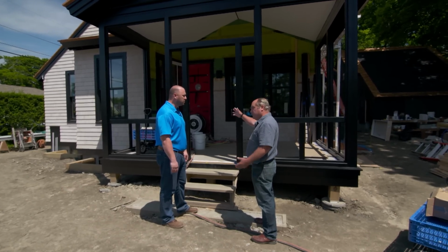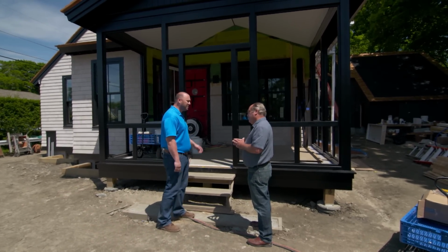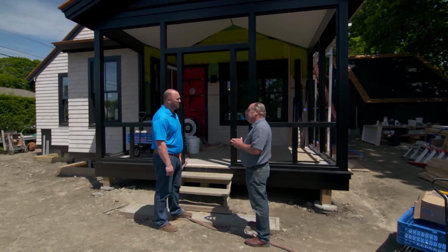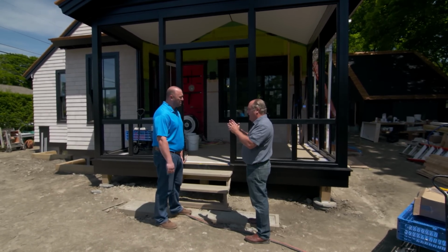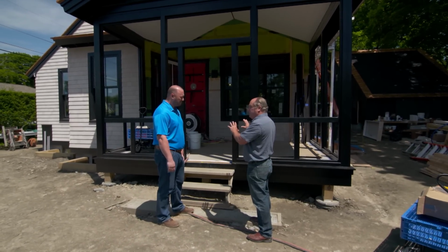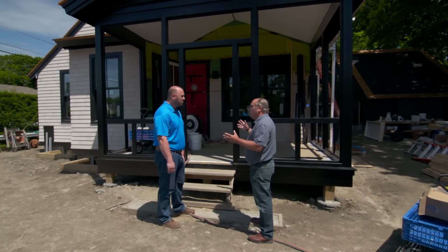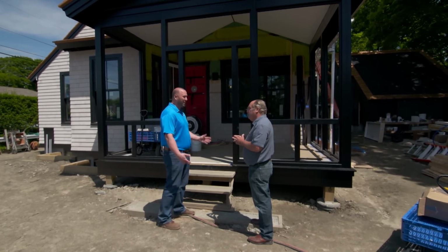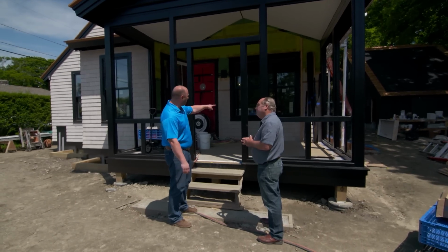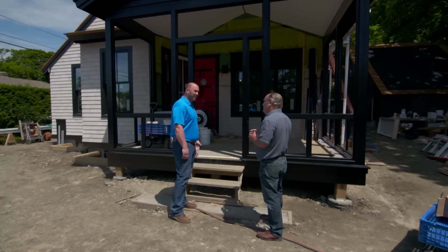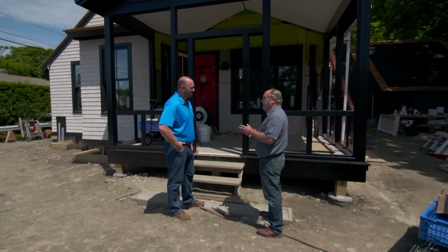How's our existing house? This is new construction. Sure, we just completed our test and we're at 3.8 ACH 50. So ACH, that is air changes per hour. How much air would leak out of the building when you're pressurizing it, right? So what's the worst? Sure, I've seen them as high as in the 20s. Okay, so 3.8, what's that equivalent to? That'd be the equivalent to probably this window being open about 5 inches or so. Under pressure. Correct. That's a lot of heat leaving out.